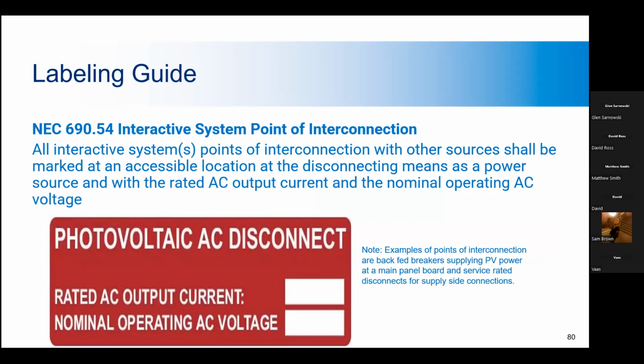Here's an example of the required labeling at the interactive system point of interconnection. You need the AC output current and the AC operating voltage. A lot of times these are missing, incomplete, or not suitable for the environment. But many manufacturers make labels that will endure outdoor conditions such as wind, rain, snow, or UV degradation. So make sure that the labels that are installed are rated for the location and the conditions, and make sure that they're accurate.